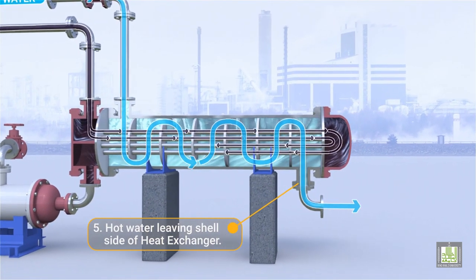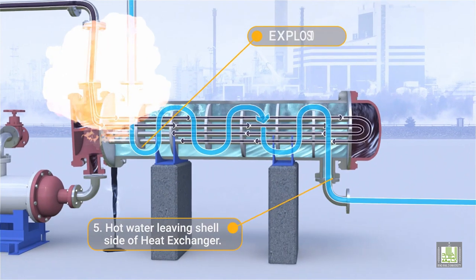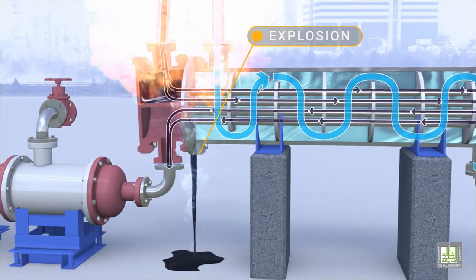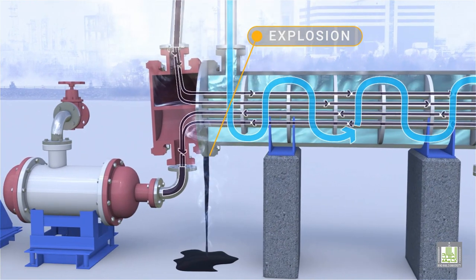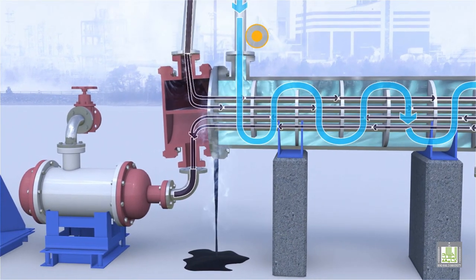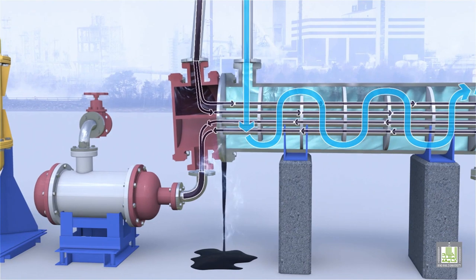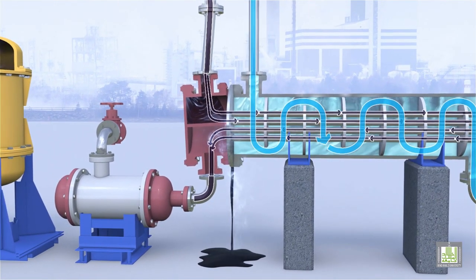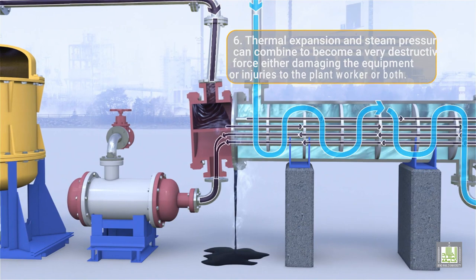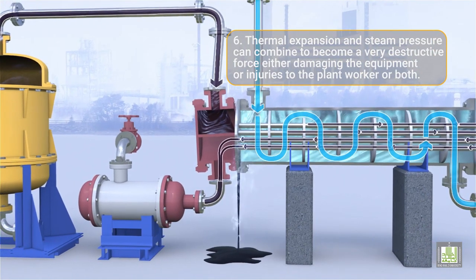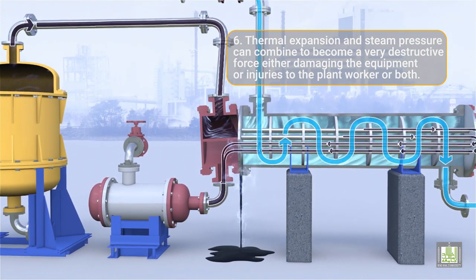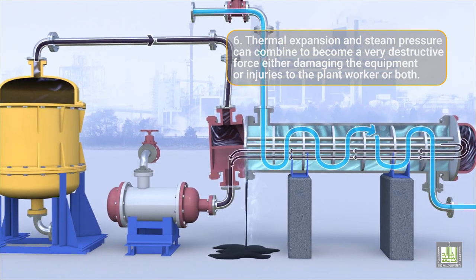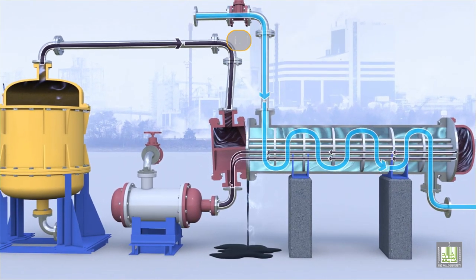The heat exchanger is typically provided with low or high point vents to remove water from tubes or the shell. Uncontrolled mixing of water with hydrocarbons can generate high pressure conditions and can damage systems that are not equipped with pressure relief devices. Thermal expansion and steam pressure can combine to become a very destructive force, either damaging the equipment or causing injuries to the plant worker, or both.